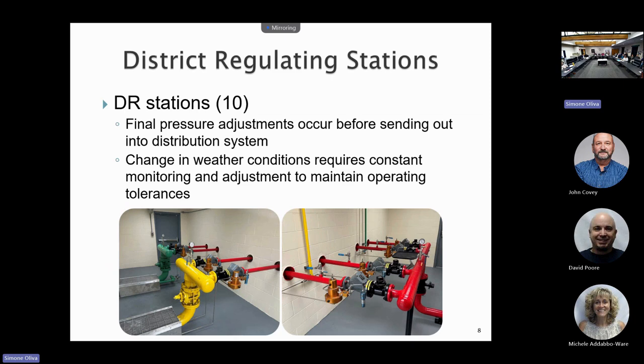This requires constant monitoring, one of the main reasons we have control room operators on 24/7, 365. They have alarm points: a low, a low-low, a high, and a high-high. So there's a level where we need to get somebody on the move, and a level where we need to get everybody on the move. The difference between low and low-low, high and high-high, is temperature and pressure.